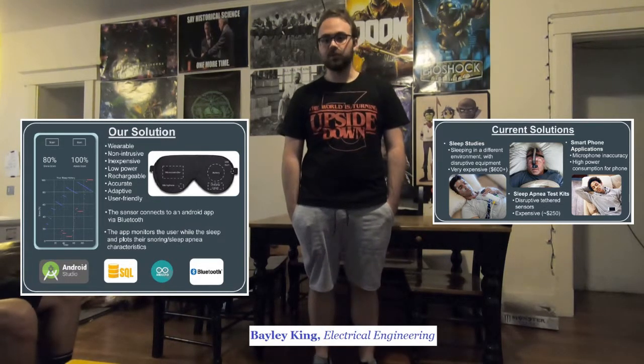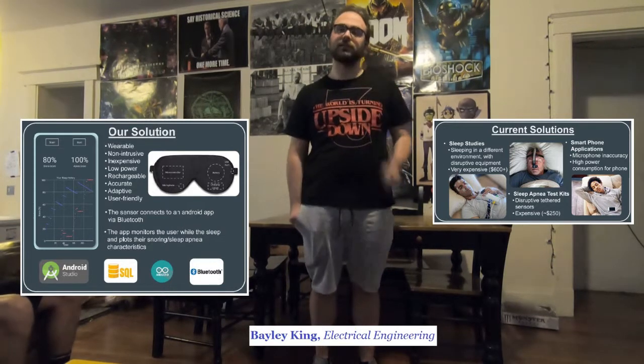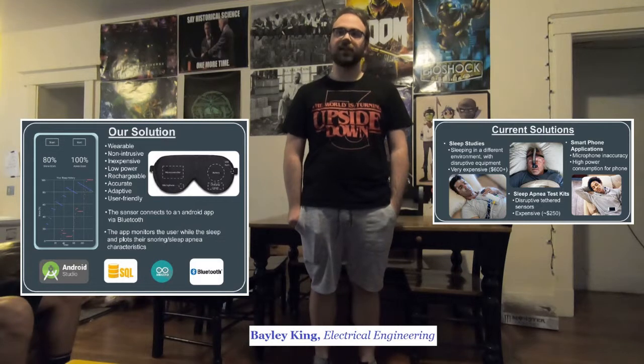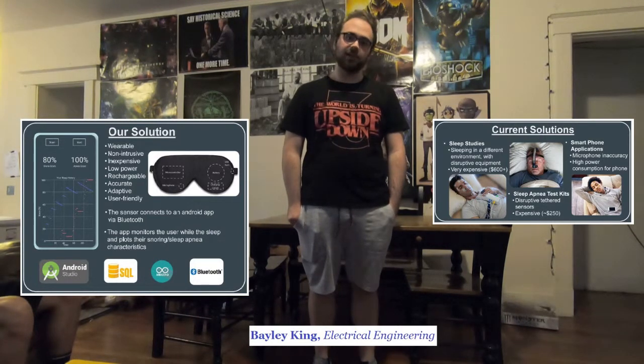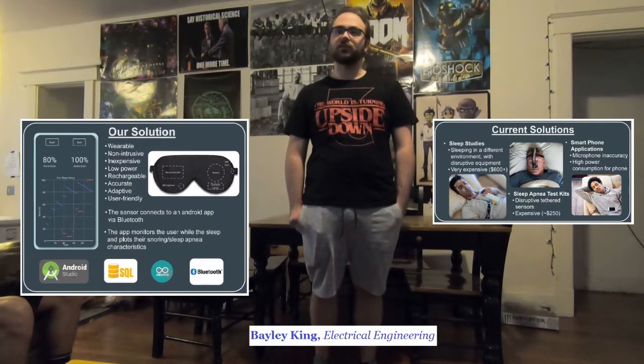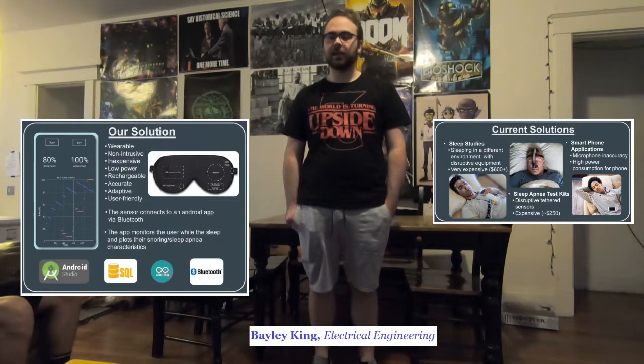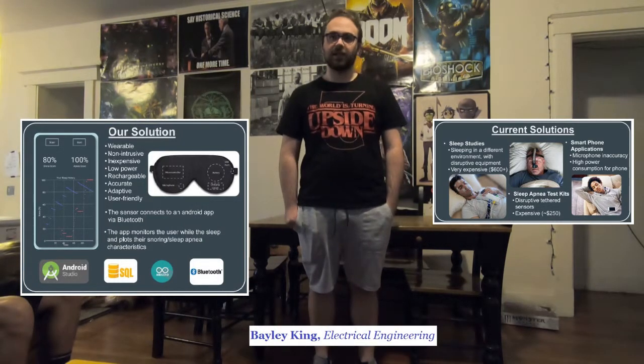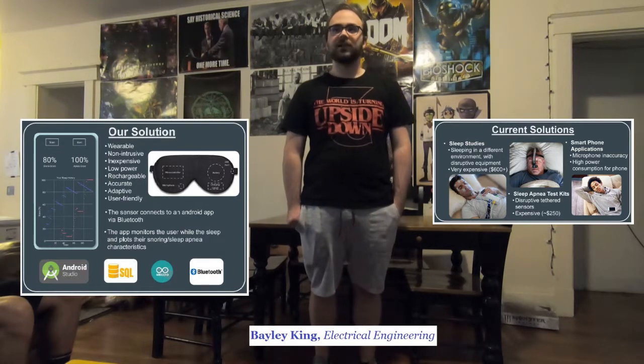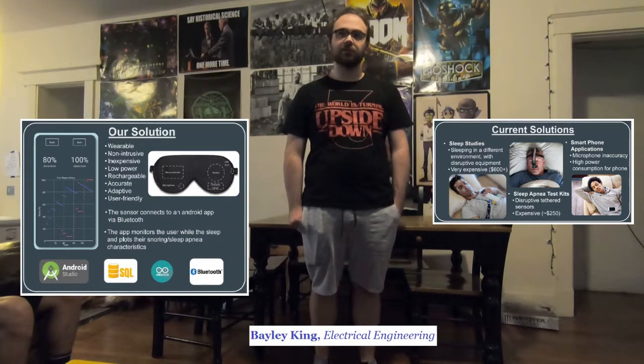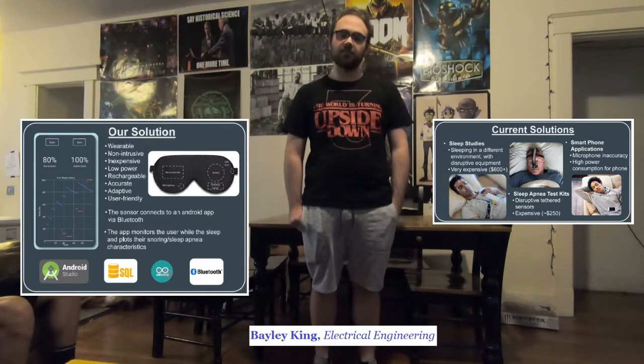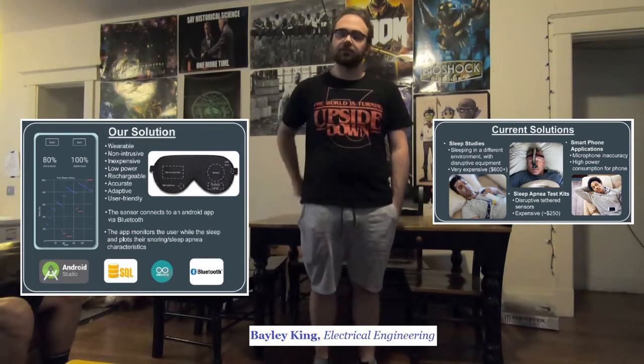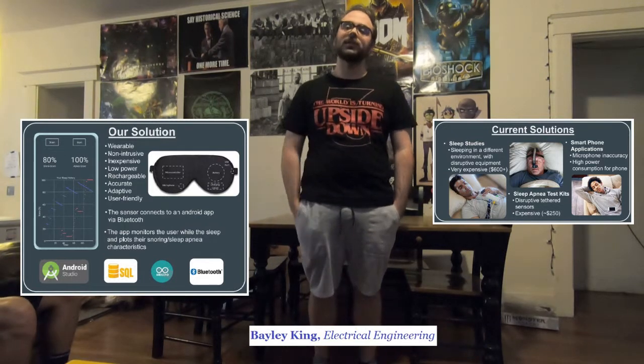The device needed to be rechargeable. For it to work normally, it has to last a full night's sleep, so we designed it for eight hours of battery life. Through our testing, we've achieved at least 10 hours of battery life, and we doubt anyone is sleeping longer than 10 hours. The device can be plugged back in and takes just a few hours to fully charge. Our battery is 500 milliamp-hours and consistently lasts at least 10 hours.